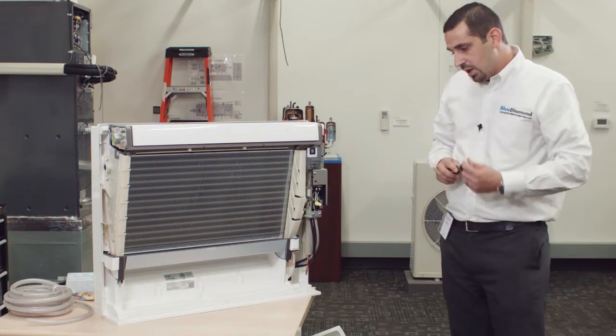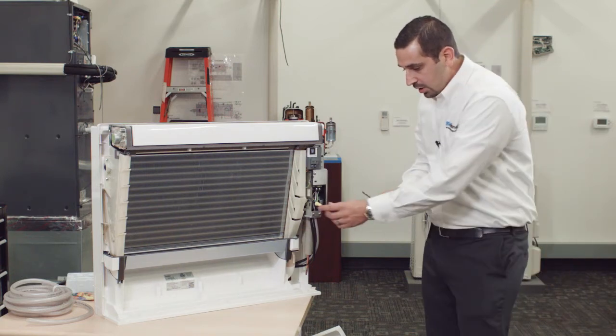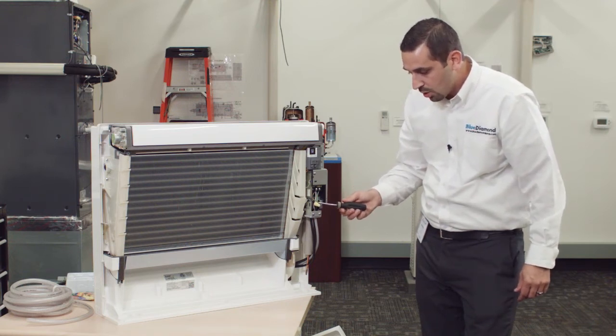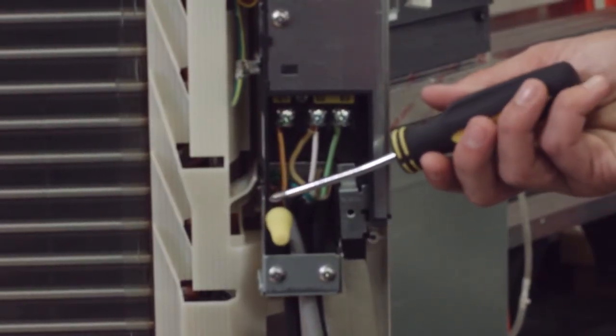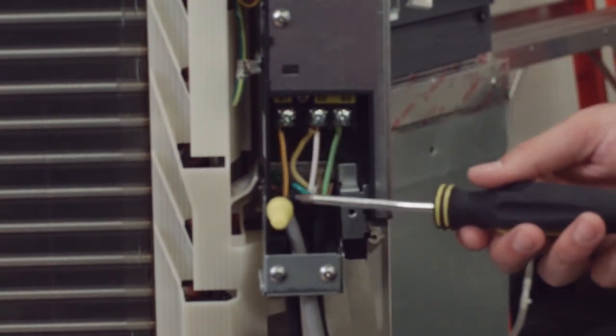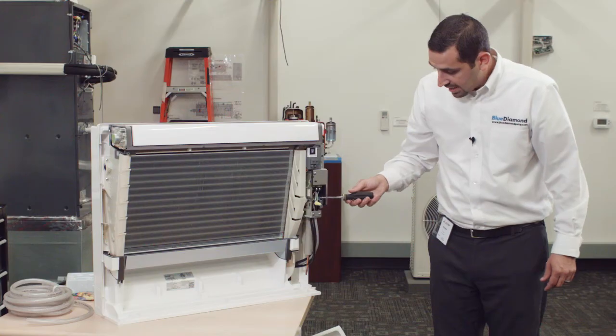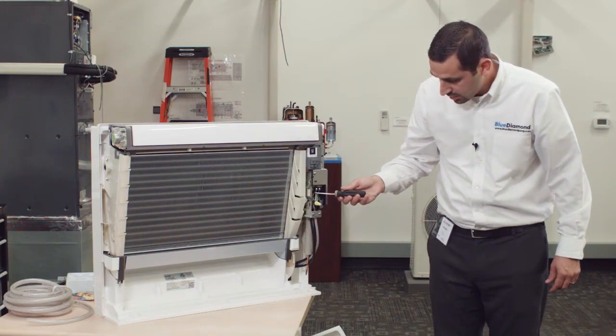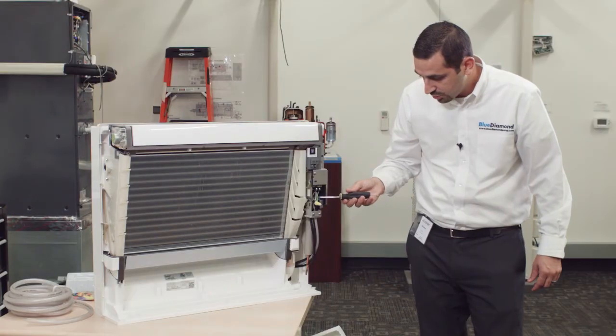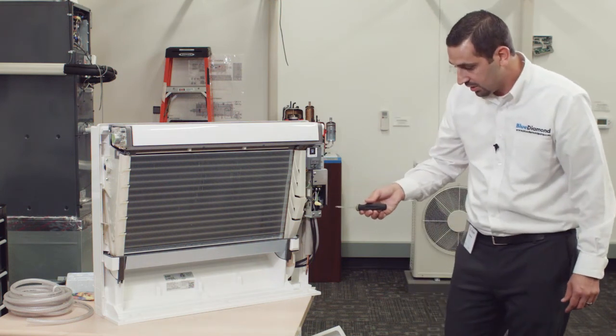Finally, you have your S1 wire run through my pump, so your S1 from your condenser is wire nutted to both of these black wires. This black wire is your L1 from my pump, this other black wire is the common from the relay on the pump. Yellow is normally closed and that's going to go back to S1. So S1 from your condenser into both black wires, yellow normally closed back out to S1 of the air handler. S2 on the air handler has S2 from your condenser right here and it also has my L2, my white wire, that's where we're going to get our second leg of power. S3 is your communication between your condenser and air handler, this is something that you do not alter, do not modify, we're not going to be breaking anything on S3.